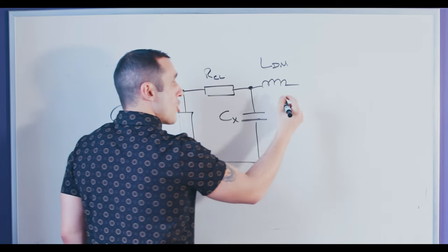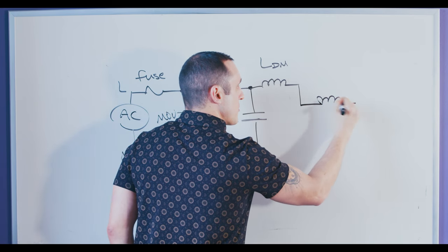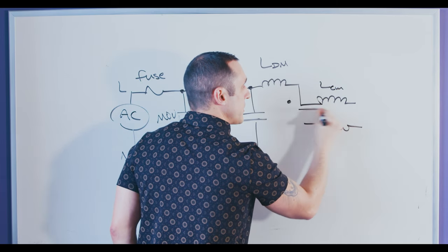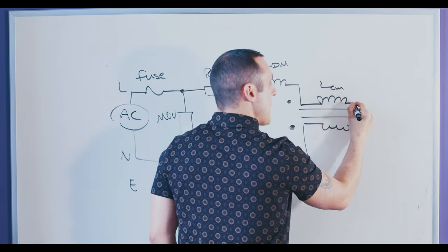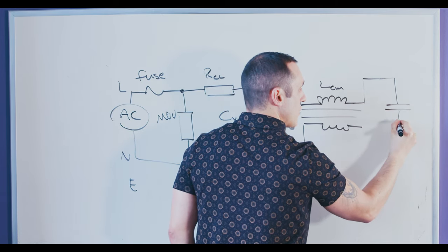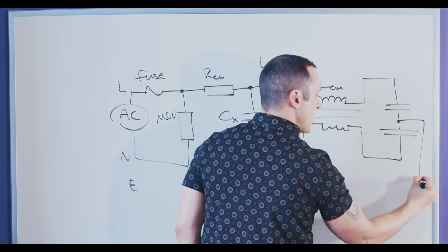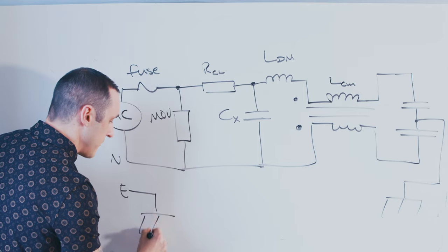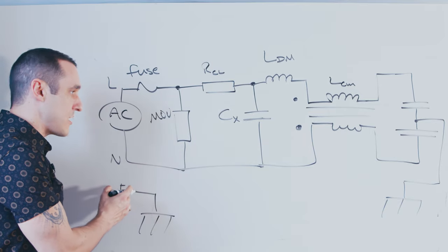After the differential mode choke, we can start looking at common mode noise. One way to do that is with a common mode choke right here — I'm drawing two coupled inductors with polarity marked to indicate it is a common mode choke. After this, you may see a couple of Y capacitors which further filter out the common mode noise, and this is where you get back to your earth or chassis connection.